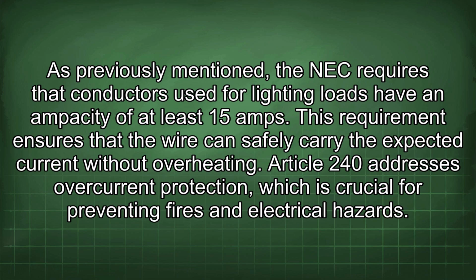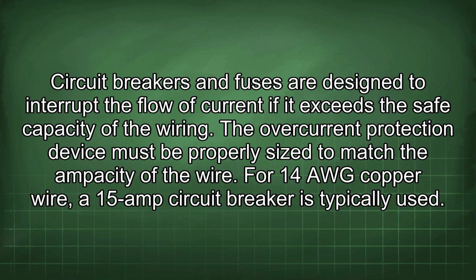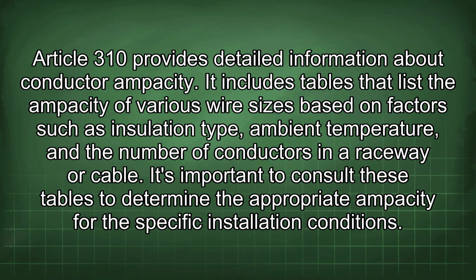Article 240 addresses overcurrent protection, which is crucial for preventing fires and electrical hazards. Circuit breakers and fuses are designed to interrupt the flow of current if it exceeds the safe capacity of the wiring. The overcurrent protection device must be properly sized to match the ampacity of the wire. For a 14 AWG copper wire, a 15 amp circuit breaker is typically used. Article 310 provides detailed information about conductor ampacity. It includes tables that list the ampacity of various wire sizes based on factors such as insulation type, ambient temperature, and the number of conductors in a raceway or cable. It's important to consult these tables to determine the appropriate ampacity for the specific installation conditions.